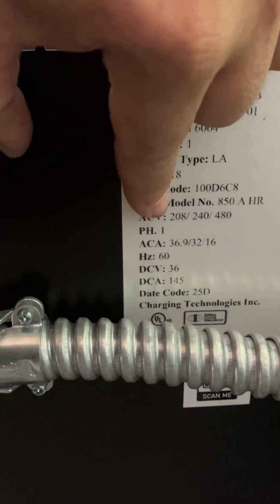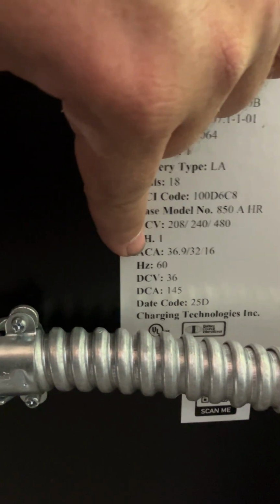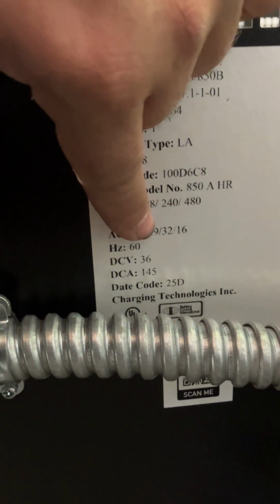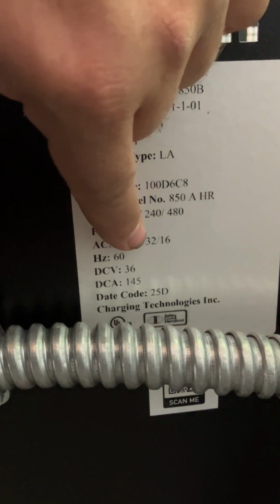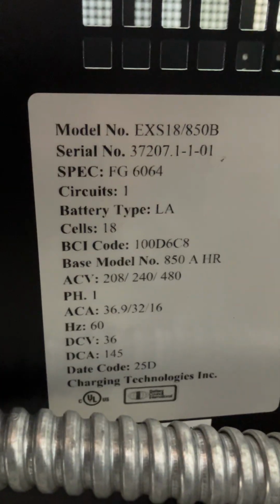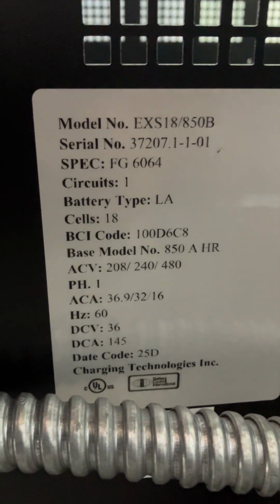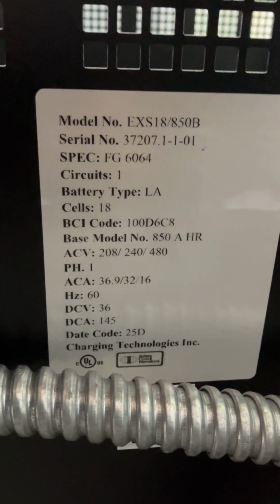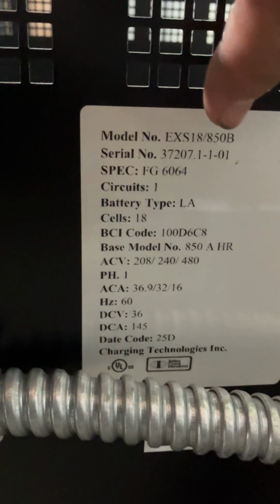Then below that it says ACA for amperage. So at 208 volts single phase it can run at the highest amperage, and at your secondary voltage, 240, it would run at the middle amperage. And if you hooked it up to 480, it would run 16 amps, which is very low. Since we have 480 available, we're going to hook it up 480 volts single phase. That's two phases out of a three-phase 480 volt panel to give us a very low 16 amp draw. And again, if you hook two phases together, they act as a single phase circuit.